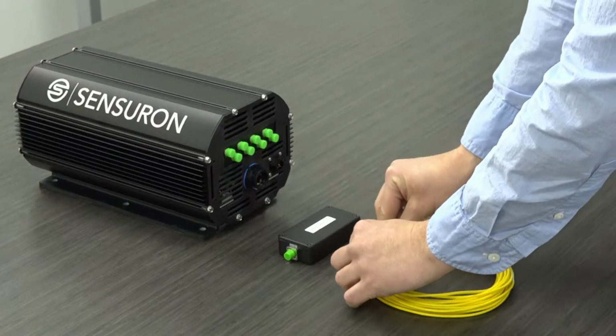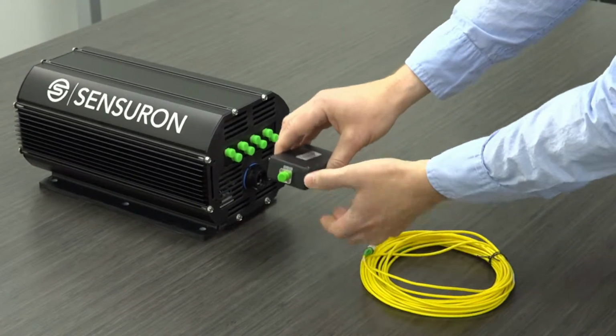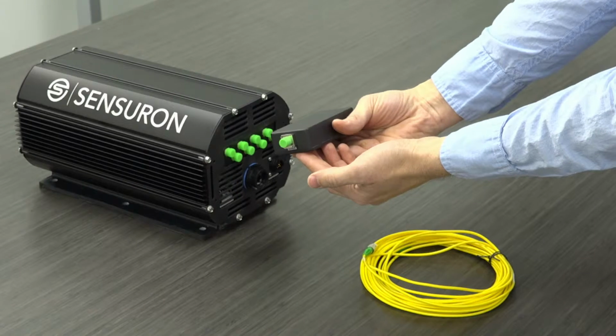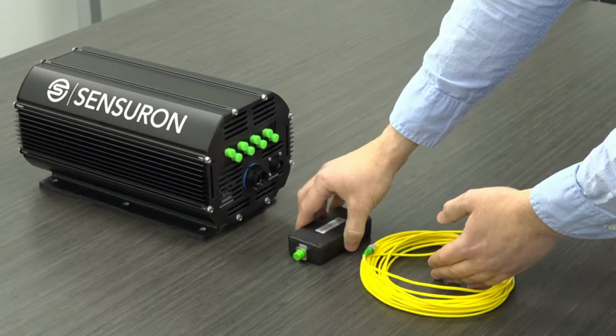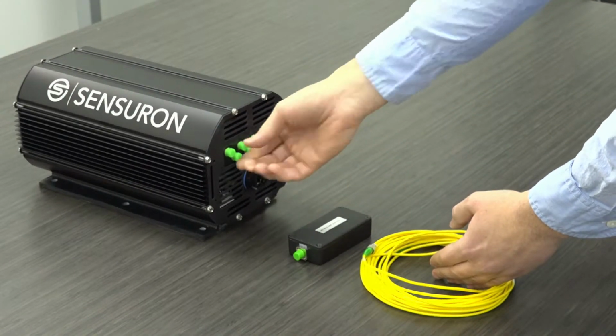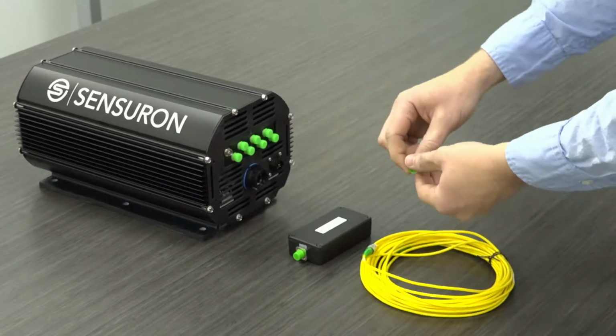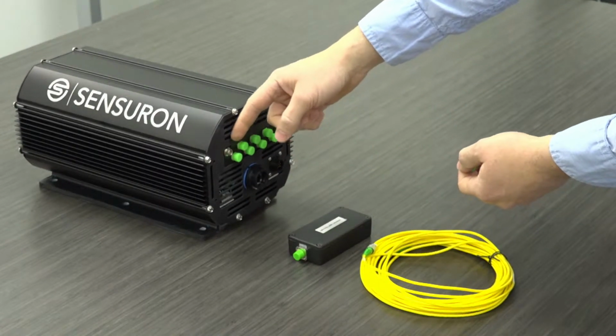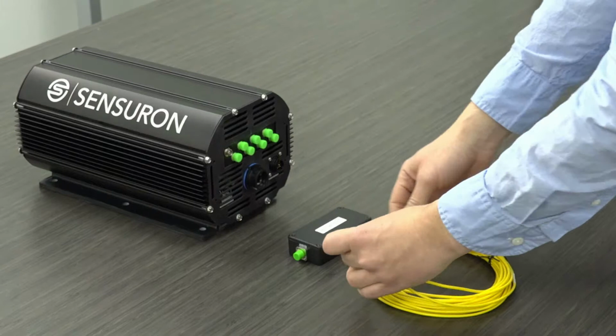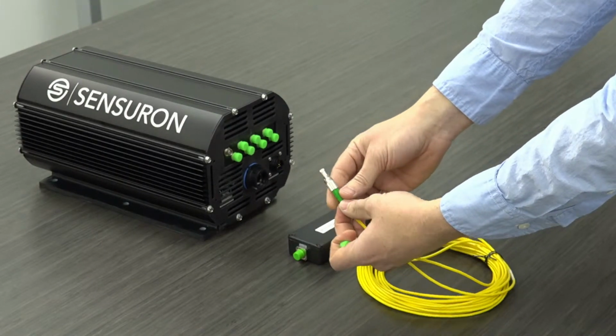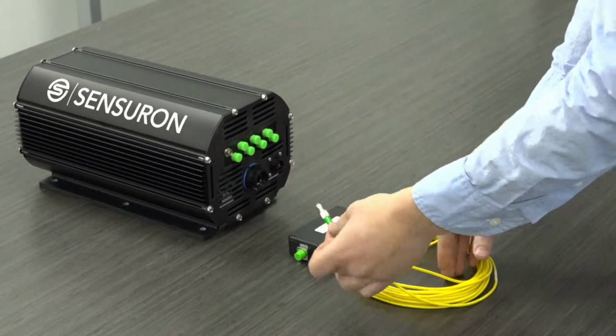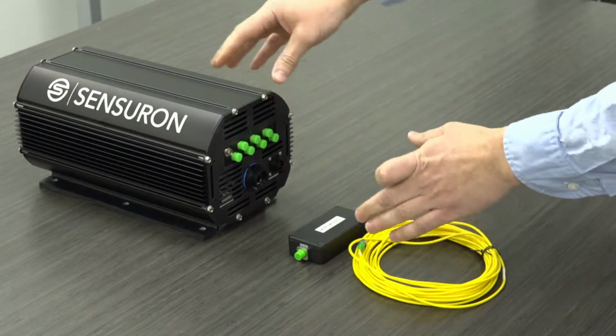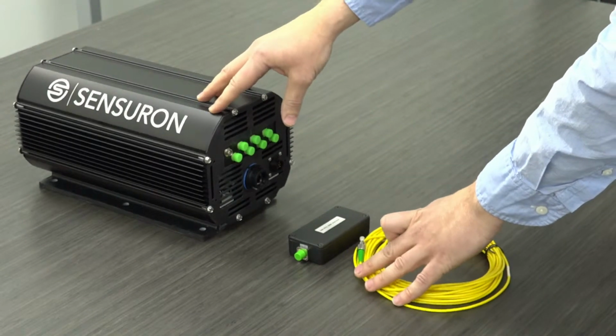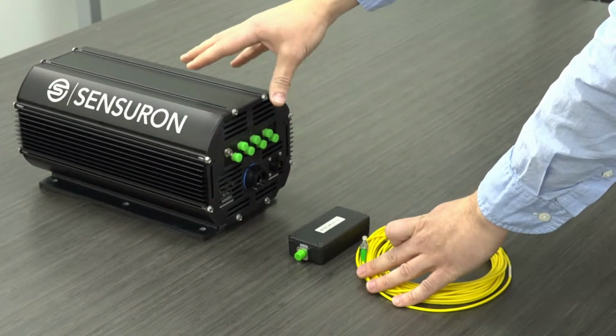On the other side of the termination, which is located on both sides of your broadband reflector, as well as the front panel of the sensing system, is an FC-APC mating coupler. So on the other side of this, there is the same type of connector here, and then you just take the exposed one that you have access to and connect it on that side. And so both of these need to be cleaned and maintained to maintain optimal use of the system.